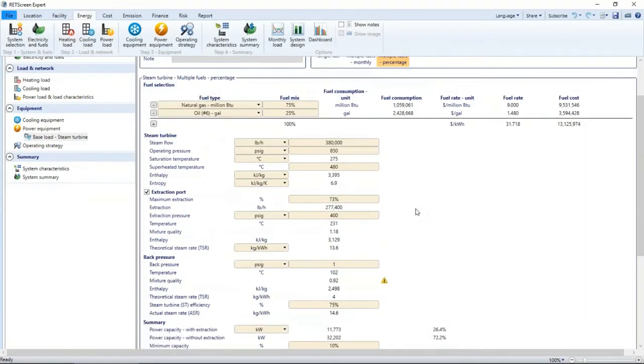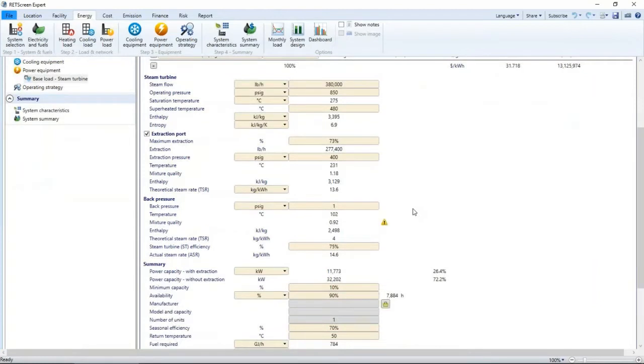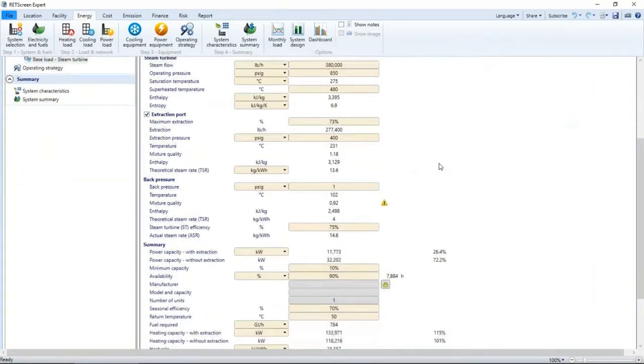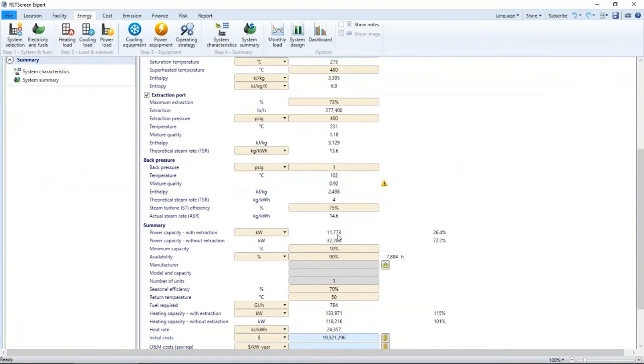In the steam turbine design, the extraction port option was selected. The model is then calculating the power capacity with extraction and without extraction. The heating capacity is also calculated for both cases. An extraction port is used to provide heat to a heating load at a higher grade, increasing the heat capacity of the system. However, in this situation, the power capacity will decrease.